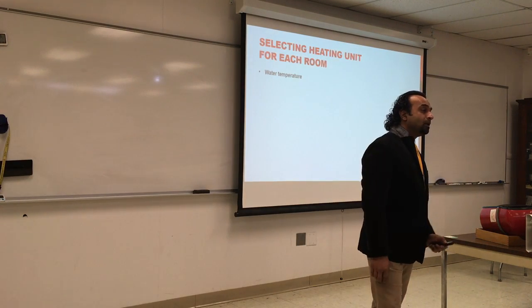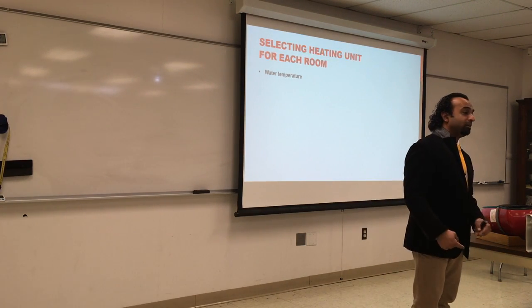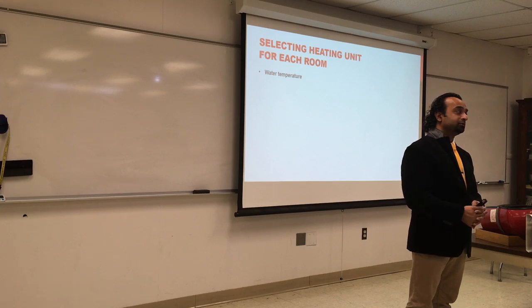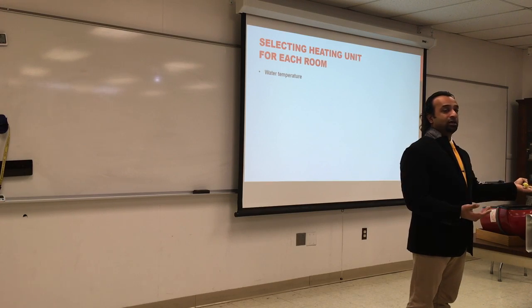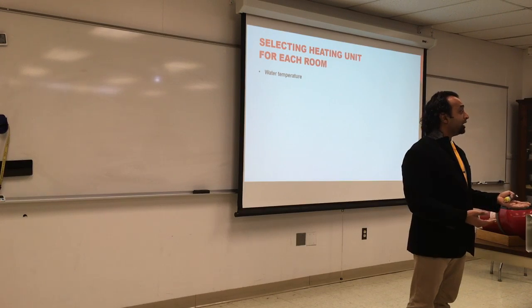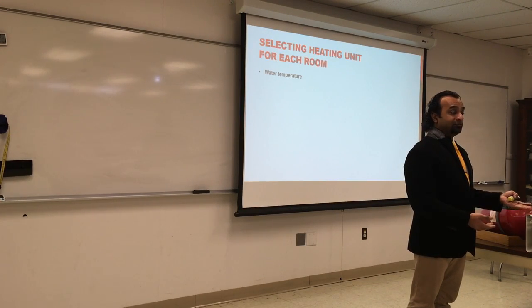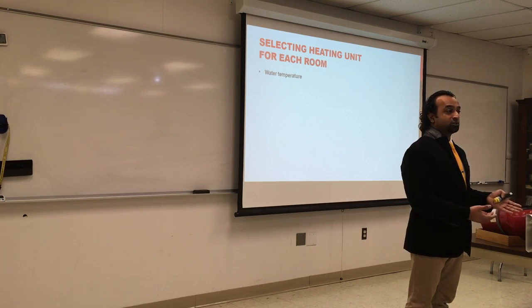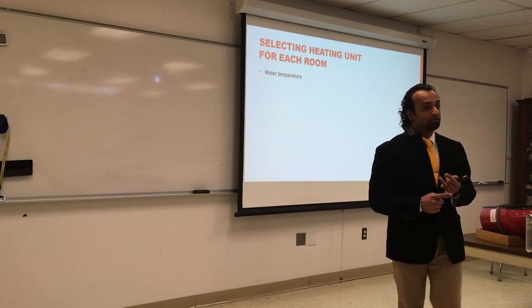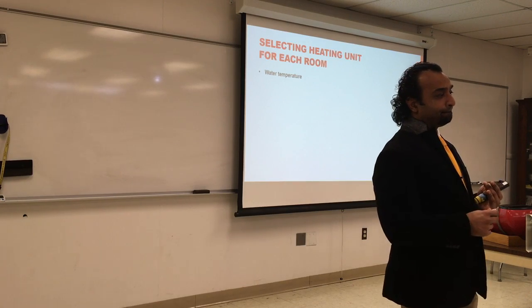And also, do you think the water that's going to come in at 180 will go out at 180? No. Otherwise, what's the point? I didn't lose any temperature. So it's going to come out at 160 degrees. It will drop at least 20 degrees at every radiator. How much? At least 20 degrees. If it drops more, it's sometimes a problem, but you want to drop at least 20 degrees. So two things go into this drop of temperature.